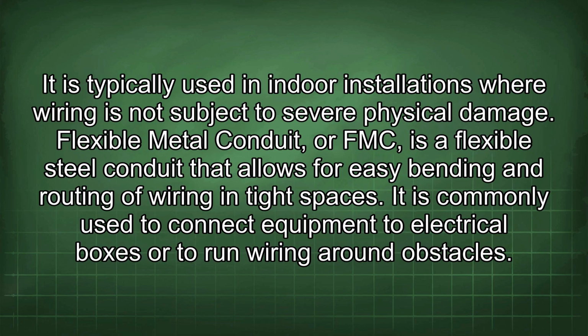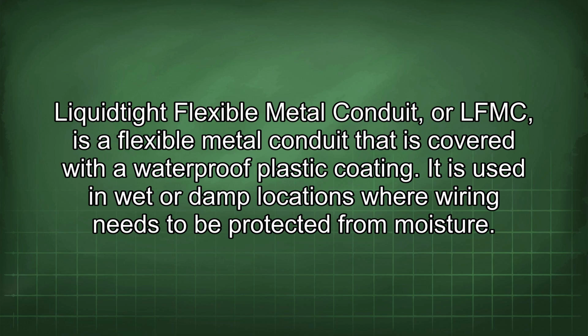It is typically used in indoor installations where wiring is not subject to severe physical damage. Flexible metal conduit, or FMC, is a flexible steel conduit that allows for easy bending and routing of wiring in tight spaces. It is commonly used to connect equipment to electrical boxes or to run wiring around obstacles. Liquid-tight flexible metal conduit, or LFMC, is a flexible metal conduit that is covered with a waterproof plastic coating. It is used in wet or damp locations where wiring needs to be protected from moisture.